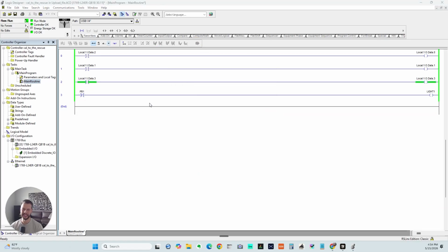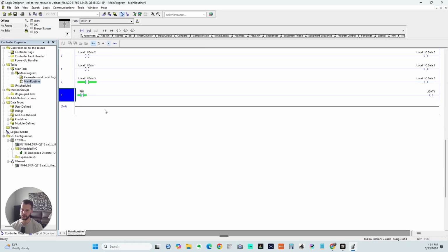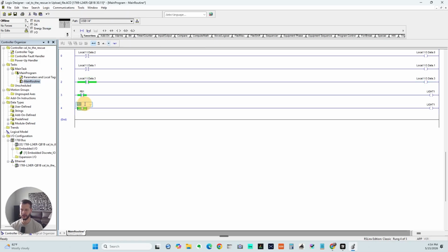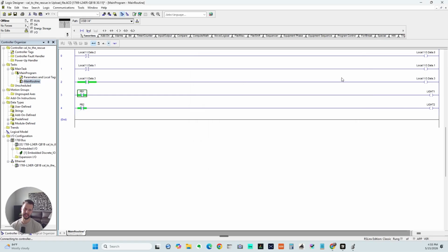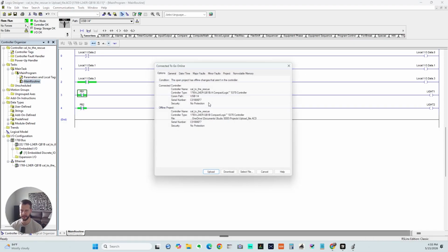Okay, so real quick, let's talk about upload and download a little more. What I'm going to do is go offline and make a change to this program while I'm offline. I'm going to create a new tag called PB2 and another tag called Light2. And then when I go to the controller and choose go online, it's going to give us an option because now the program in the controller does not match the program I have here on my computer.